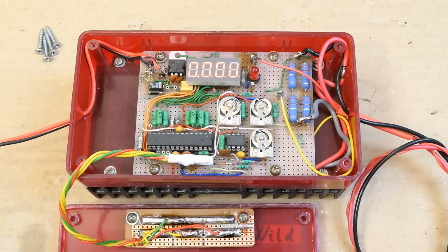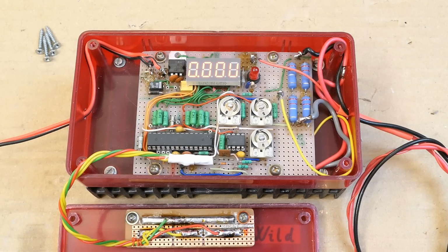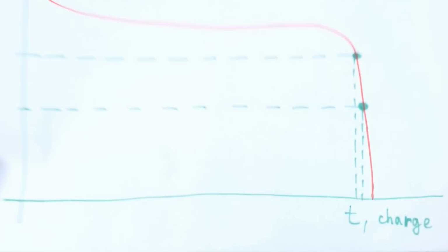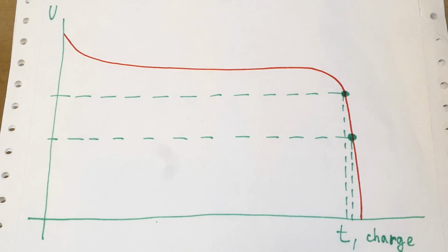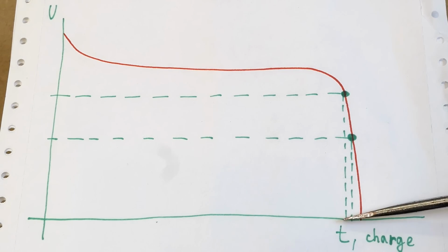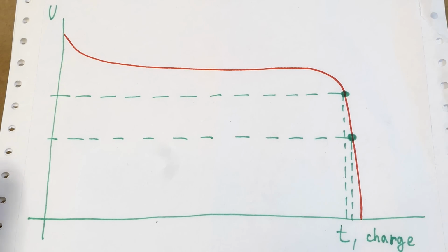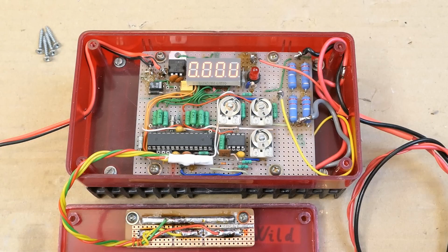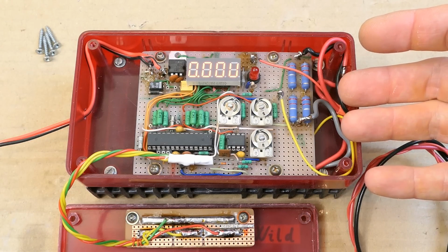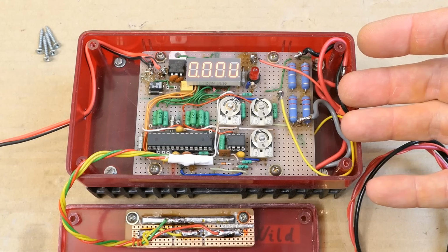And if you're asking about the accuracy of it, well, there are 3 factors. The time measurement, the voltage measurement, and the current regulation. Using a crystal, the time is measured more accurately than anything else here. And the voltage measurement matters for the termination voltage, but the discharge curve of most batteries at the end is quite steep. So even a big difference in the termination voltage causes just a small difference in the measured capacity. So the voltage measurement isn't critical either here. So the accuracy of the capacity measurement mostly depends on the accuracy of the constant current circuit.